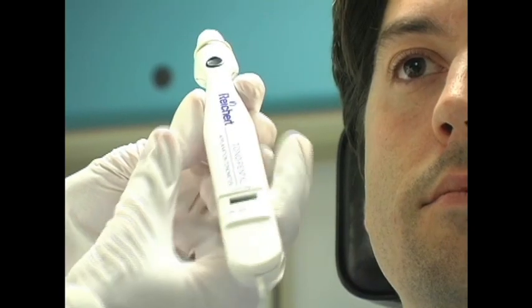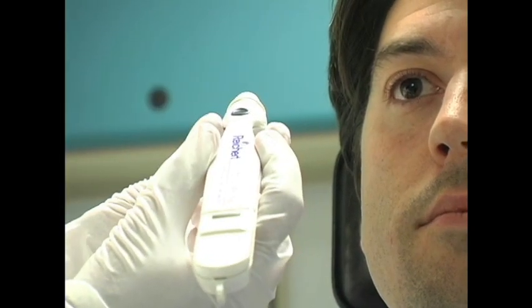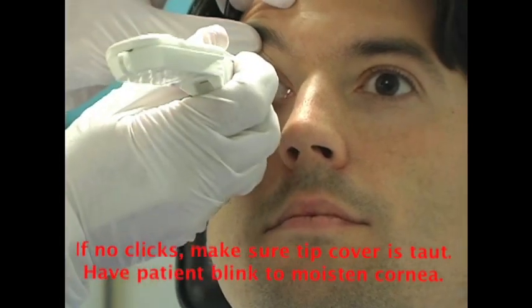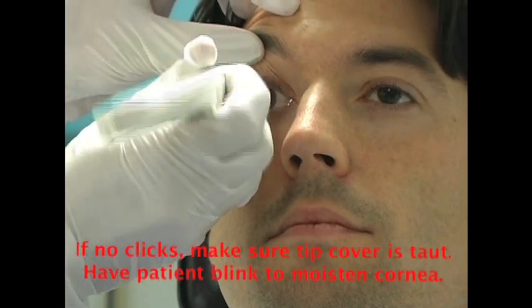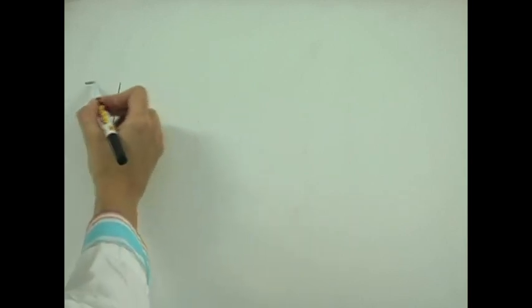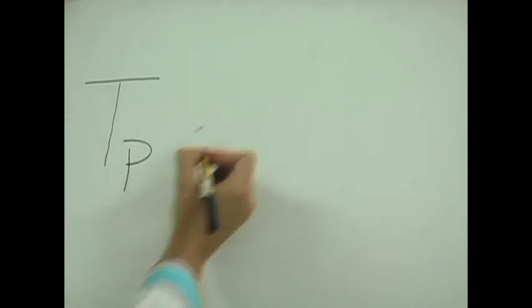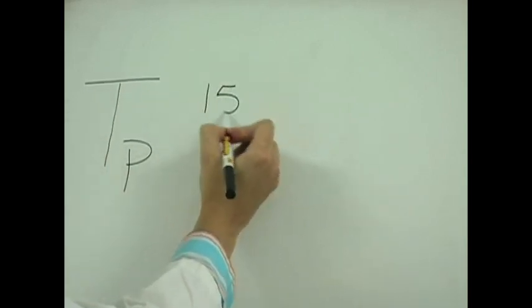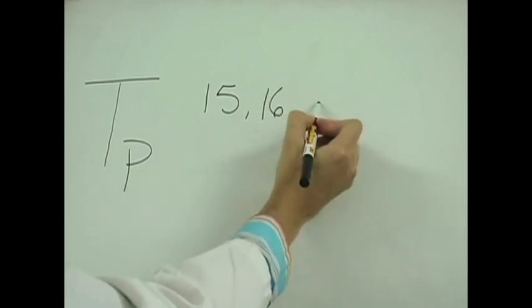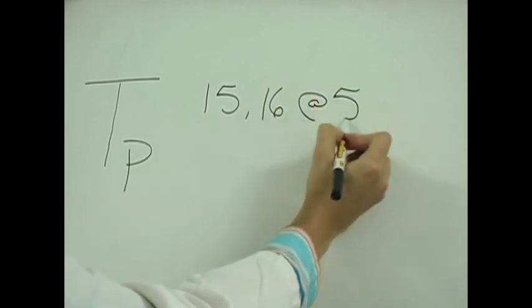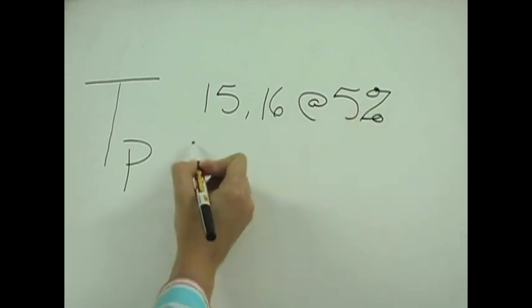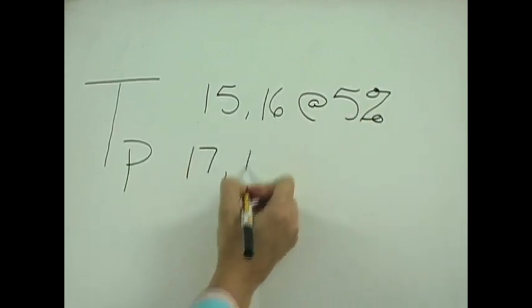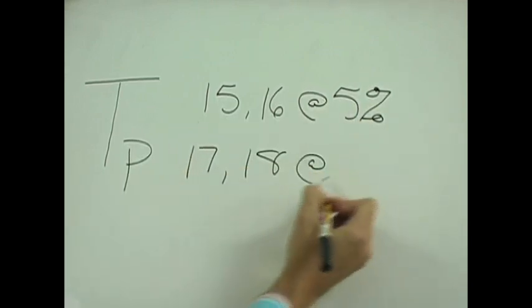Press the operator button again, and after the beep, repeat the measurement. It is best to get 2 IOP readings for each eye and record both. Measurement should be repeated until both recordings have less than 5% error. If this cannot be obtained, you should record the amount of error in your exam note. When recording the IOP, conventionally the right eye is listed first, followed by the left eye.